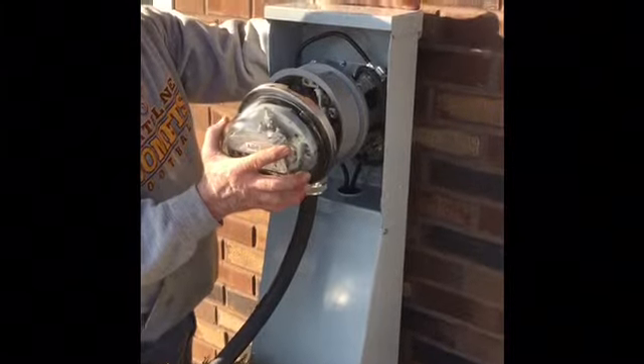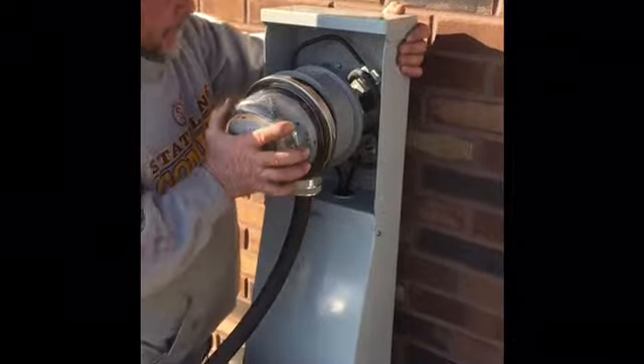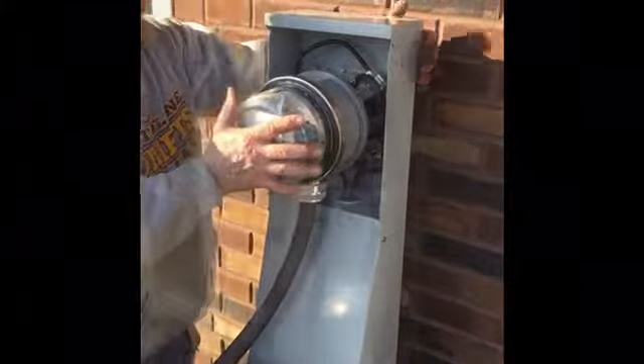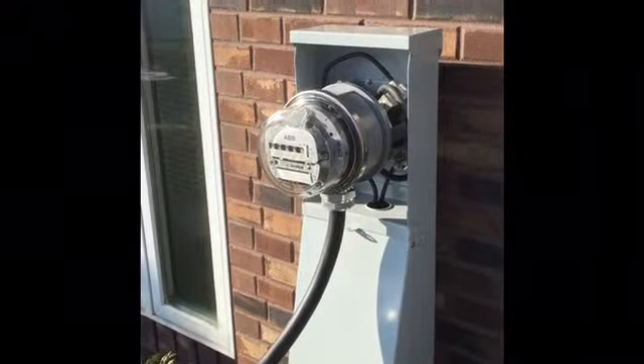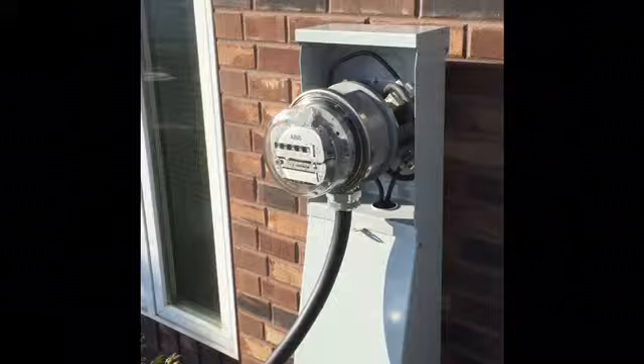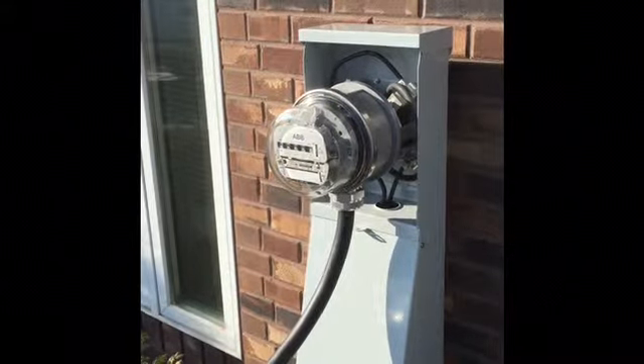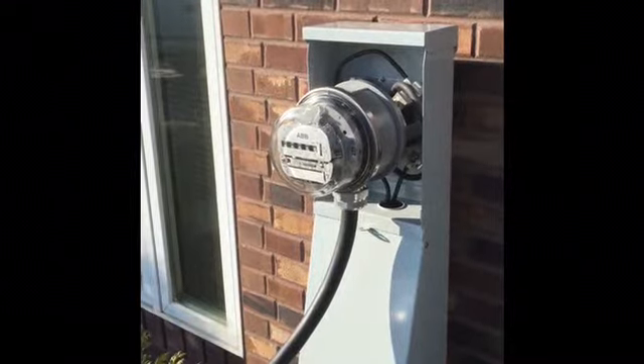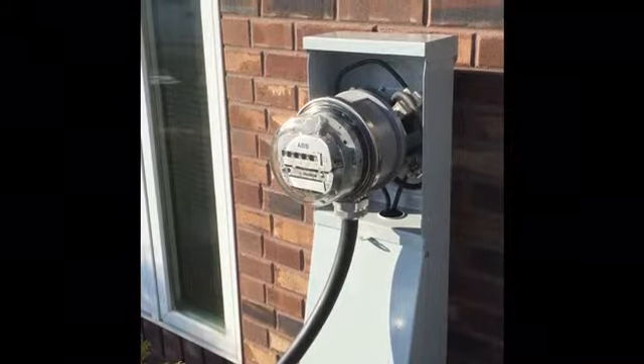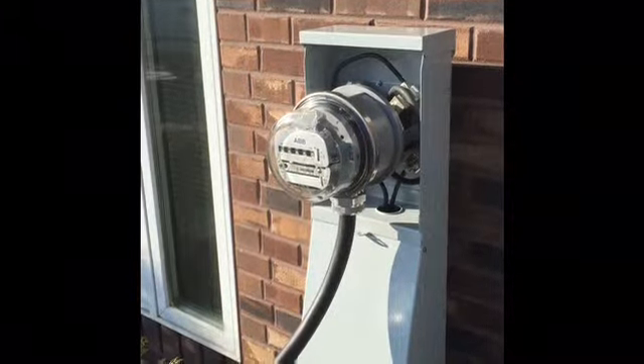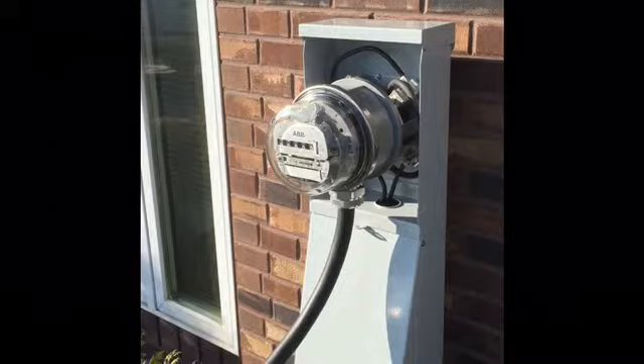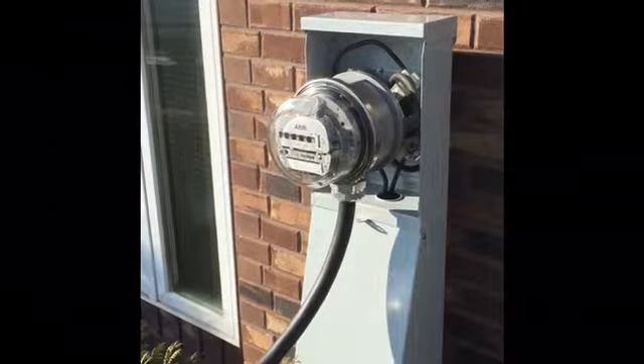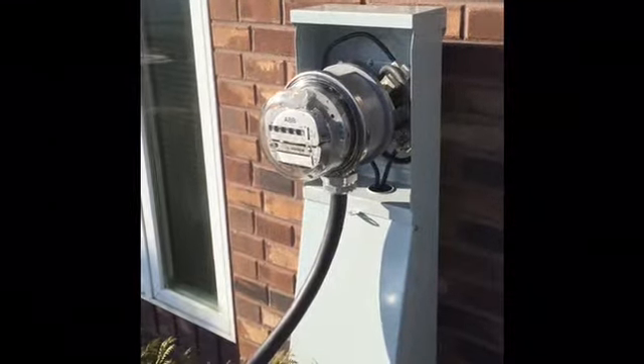Okay, now the next step, we're going to put the meter in. So after we've got the test configuration set up where we have the meter adapter in with the meter without the cover on, we're going to test the voltage and then test the neutral current and then the neutral pigtail to make sure we're not exceeding the transformer rating.